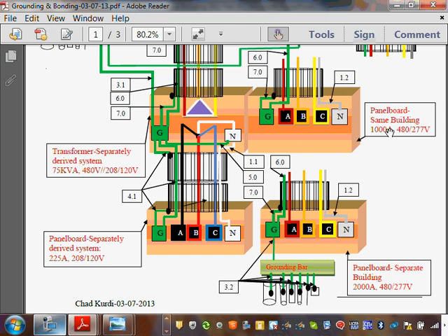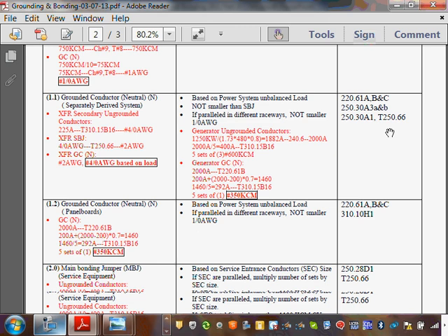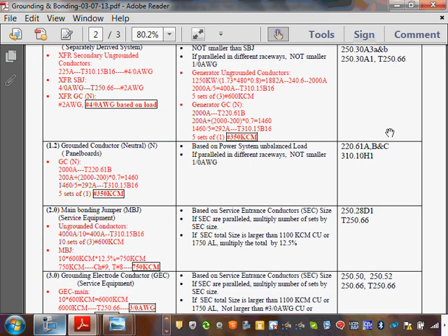I have the neutral, guys, 1.2 and 1.2. I size the neutral for you. This is also called the grounded conductor. If you guys go 1.2, I size the neutral 1.2. This is the grounded conductor for the panel, for the 2000 amp panel.